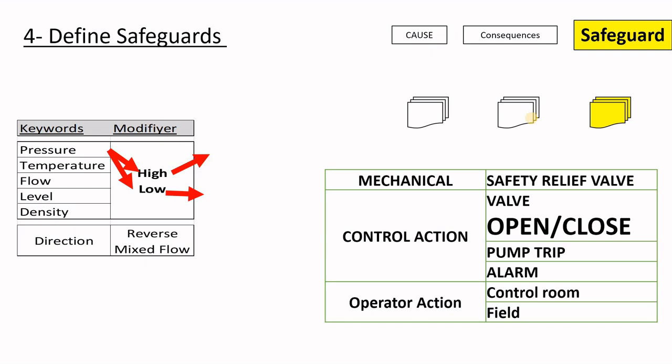In general, most of the time you can say, I have a mechanical safeguard. I have a safety relief valve which prevents the pressure from going over and beyond the design. You may say, I have a non-return valve, that is purely mechanical. And then you can say, no, it's not. We need two in series because normally non-return valve leakage is about 10% or something. Then it's not acceptable. Then you need to add more.